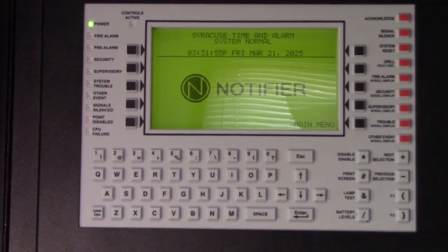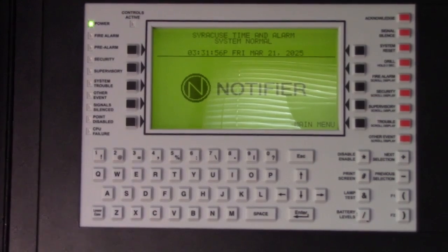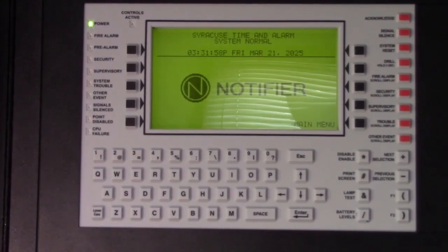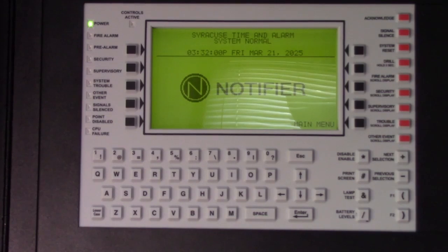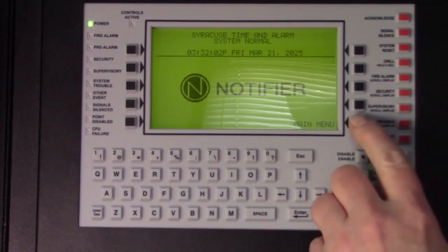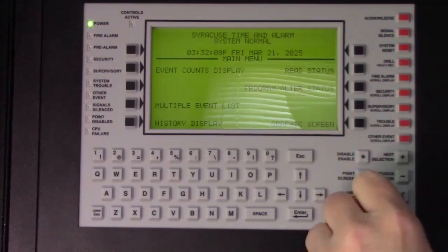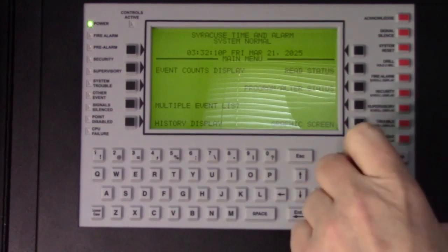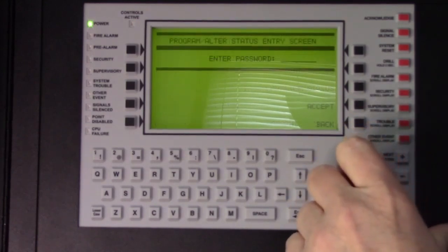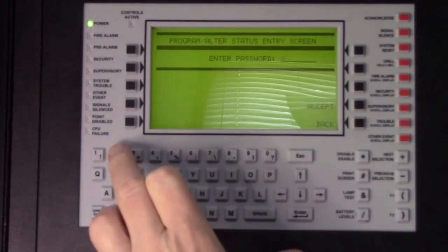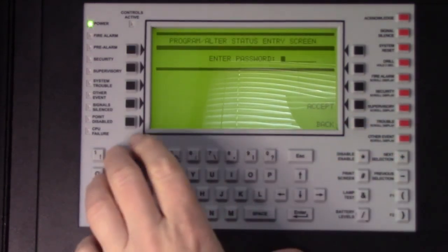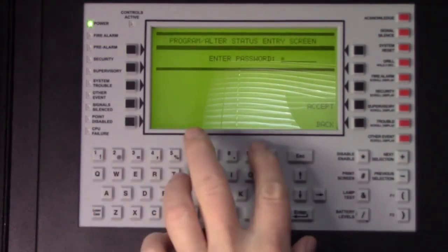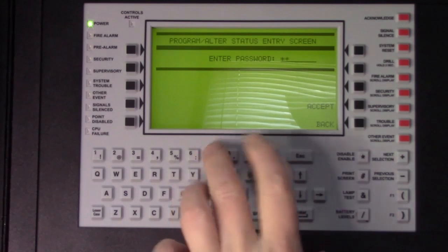In order to connect your laptop to the printer port of a Notifier 3030, it needs to be turned on and set to the correct settings. Start by pressing main menu, then program, alter status, and enter your installer password for your particular system.